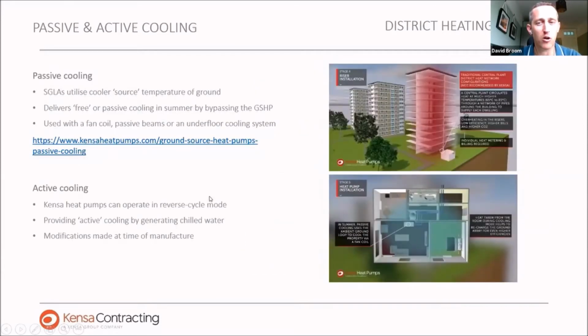One of the other benefits of having the distribution system on the cold side of the heat pump is that we've essentially got a chilled water infrastructure arriving at each property, probably more relevant to new build than retrofit. In new build properties, overheating is becoming increasingly an issue compared to underheating in winter. By using a heat pump, we can use that chilled groundwater infrastructure that reaches each property, bypass the heat pump, and provide what we call passive cooling into the dwelling. An interesting option if you're looking at new builds.